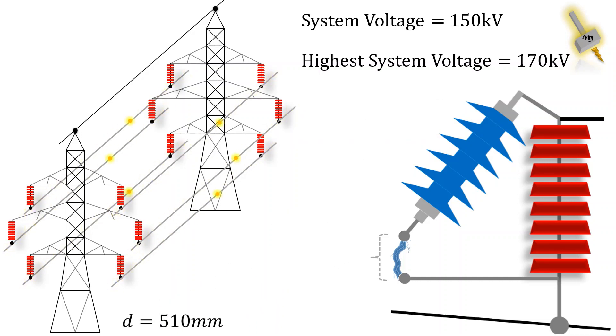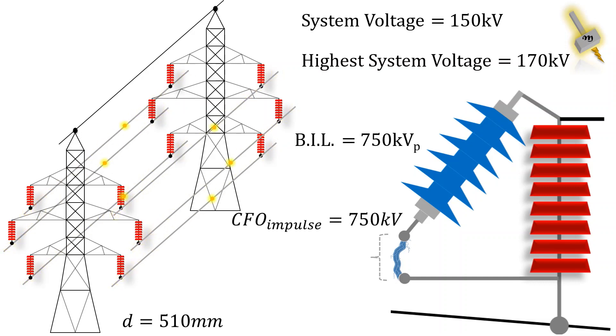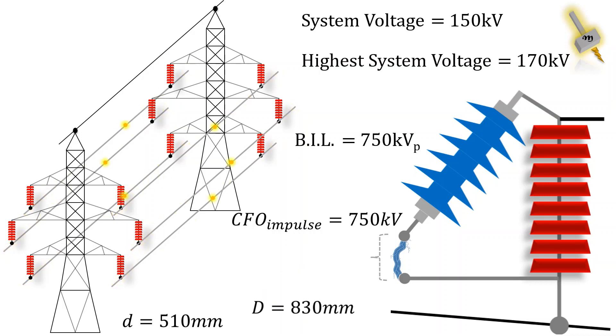For the same system, the BIL will be 750 KV peak. Considering a rod-rod electrode configuration, the gap factor will be 1.3. The maximum spark gap distance will be 830 mm.